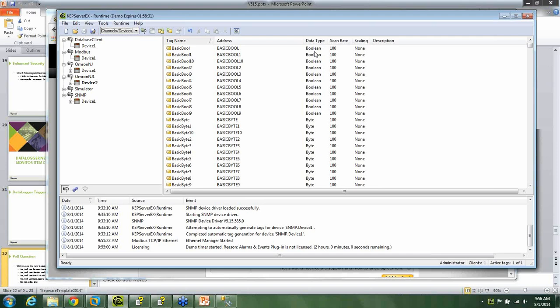And then another question from Daniel: is there a way that data logger can log directly to a text file like CSV? No, there's no option right now for data logger to log to text or CSV, but there is a workaround. If you have small data sets, so it can't be a huge amount of data, you can connect that to KEPServerEX with Excel using our DDE interface and save that data from Excel to CSV files.